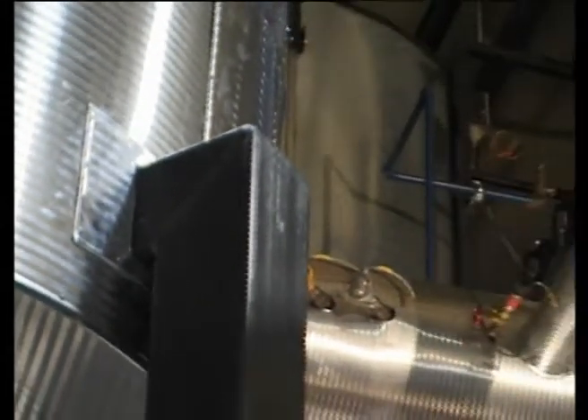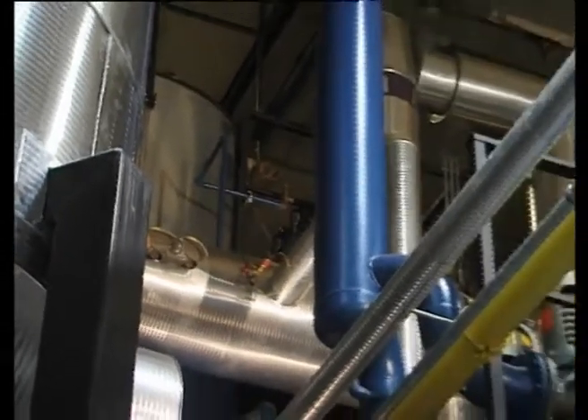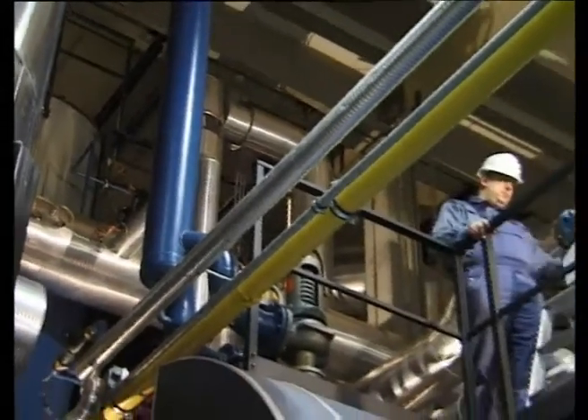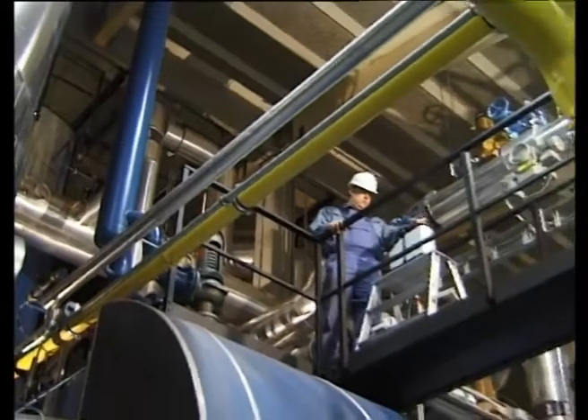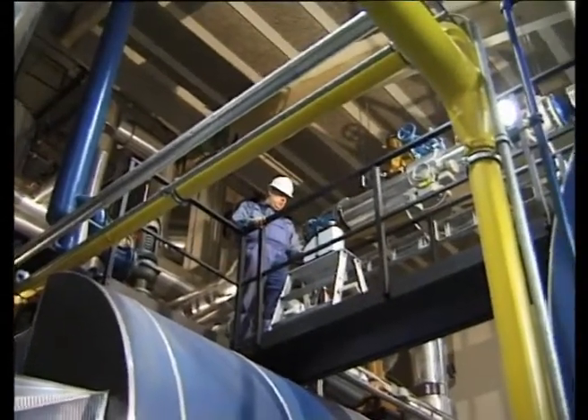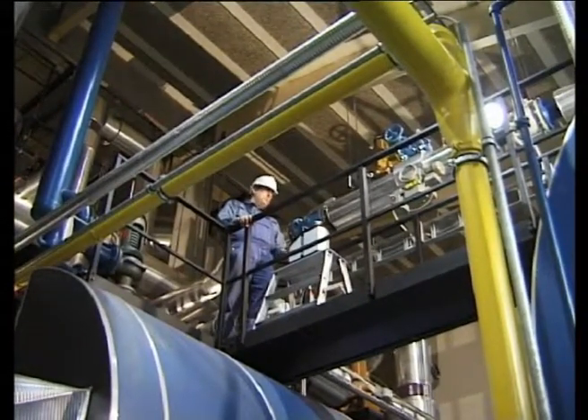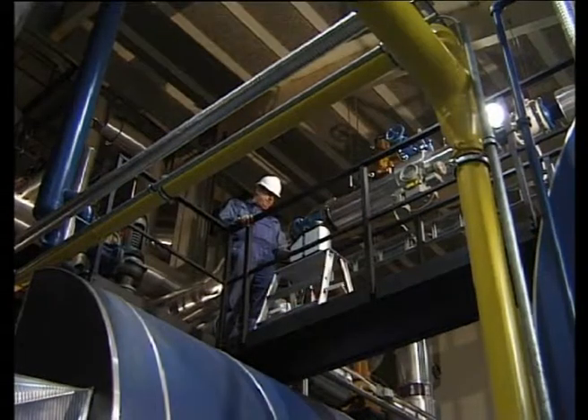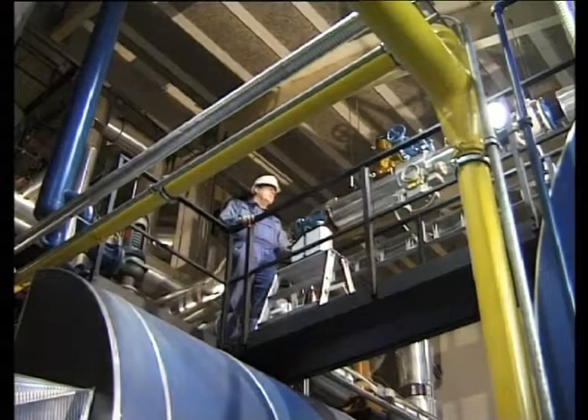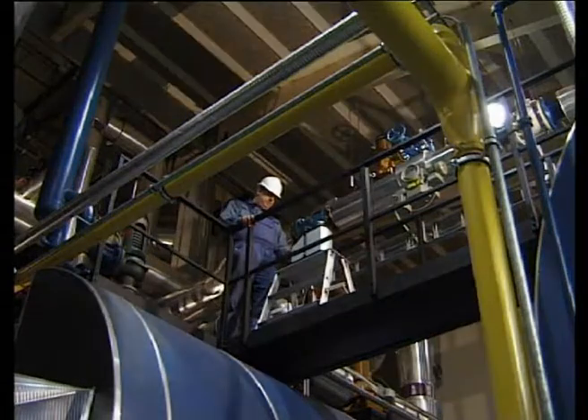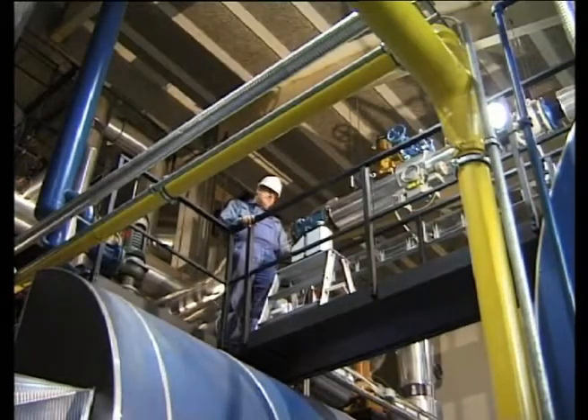Ametek has identified a great risk for inaccuracy in on-site calibrations: an unstable main supply. Large electric motors, heating elements, and the like switch on and off in the production environment. This means that the temperature regulator in traditional temperature calibrators becomes unstable. Sometimes this may result in as much as several degrees deviation.